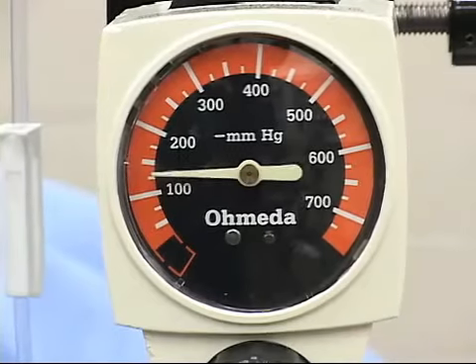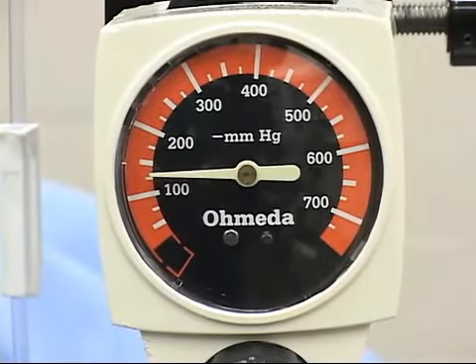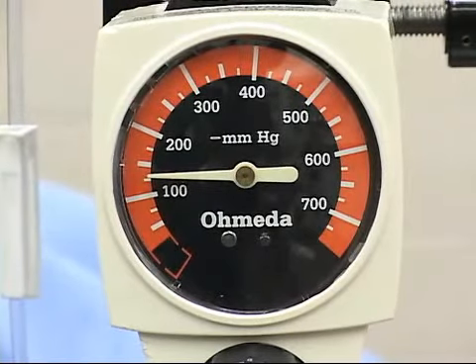Set the vacuum gauge to approximately 120 millimeters mercury and no higher than 200 millimeters mercury. Vacuum levels exceeding 200 millimeters mercury may cause hemolysis. Important to note, the American Association of Blood Banks recommends setting the vacuum at a level of 200 millimeters mercury or below for optimal red blood cell recovery.